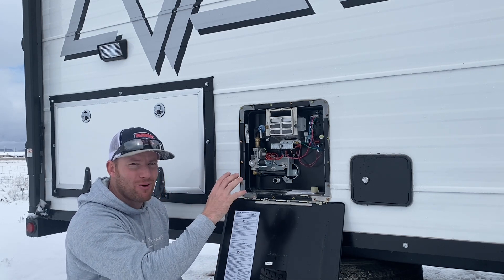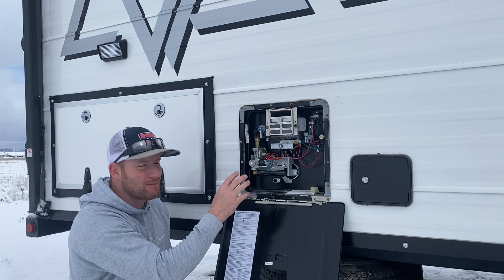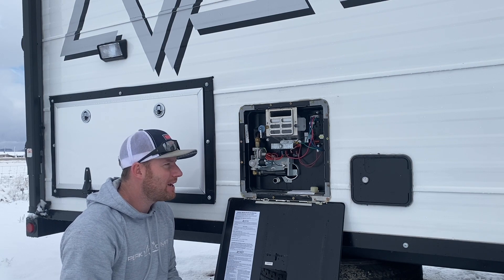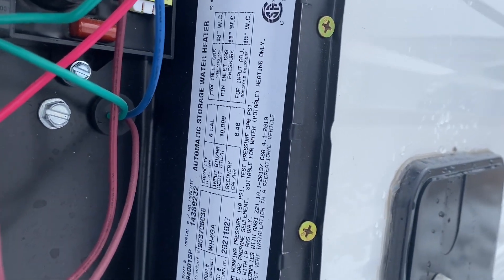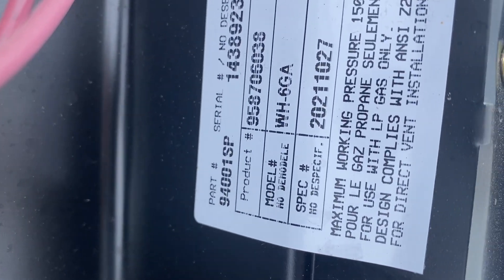I'll do a cutaway showing you what that thermal protector is, what it looks like when it's burned out, and then we'll go through how to replace it. This is a Dometic water heater — it's a six gallon, gas only, model WH-6GA.